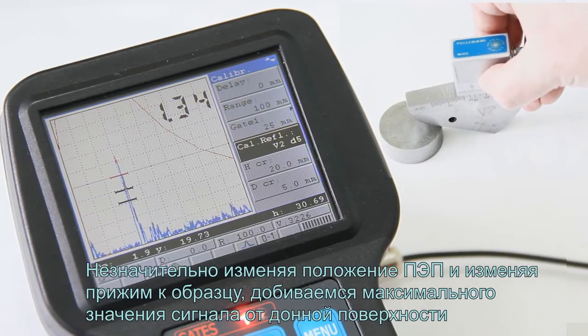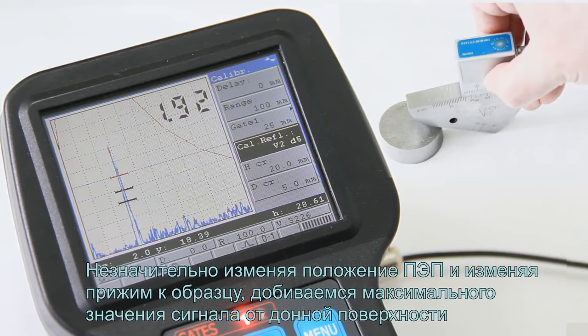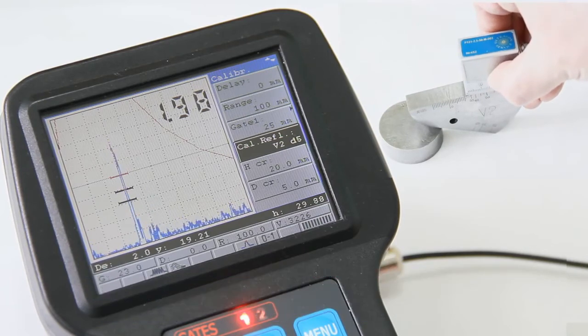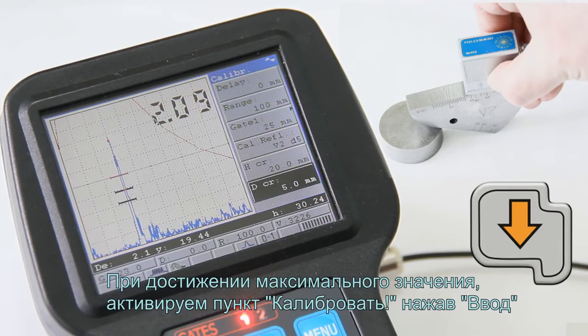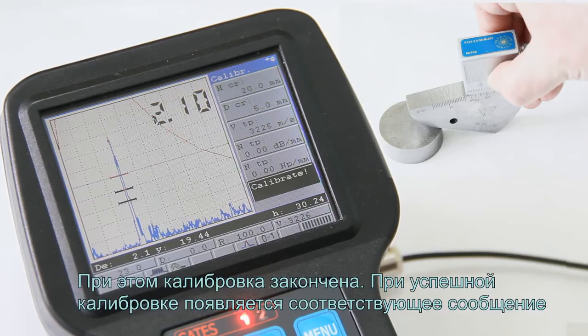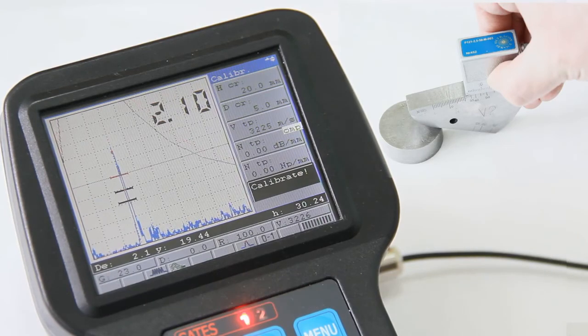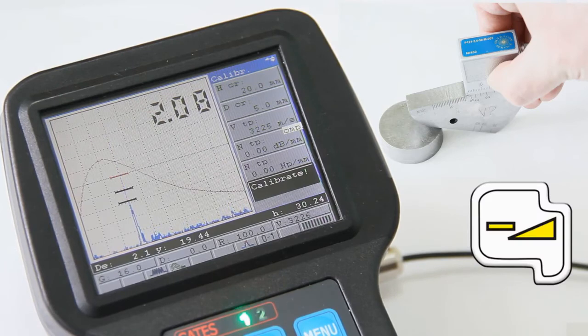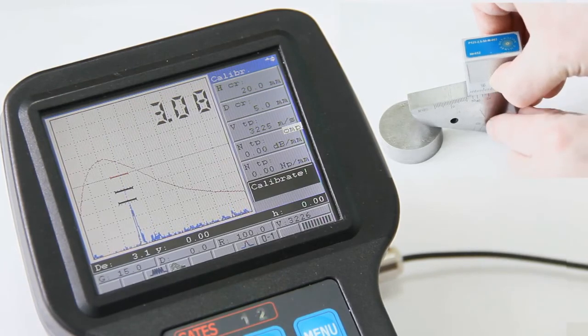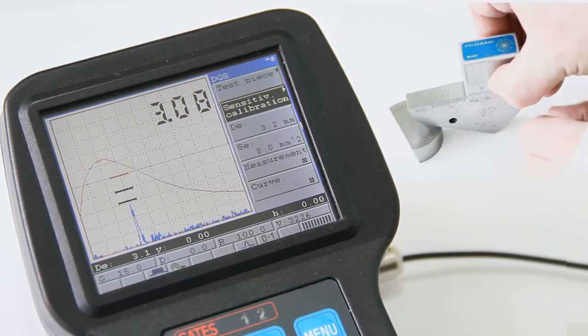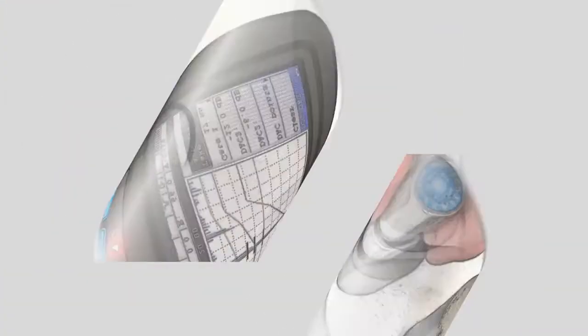Slightly change the probe position and change the probe pressure to the block to achieve the maximum backwall echo. Having achieved the maximum value, activate the calibrate item by pressing the Enter key. The calibration is finished. In case of successful calibration, the following inscription is appeared. Creating the DAC curve.